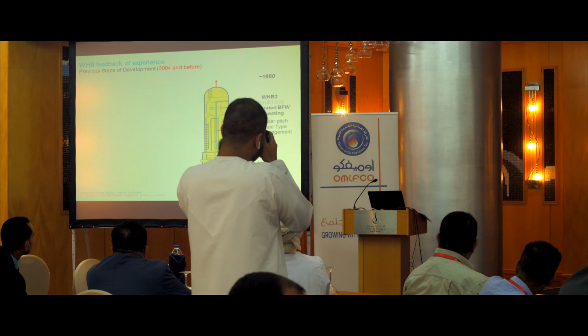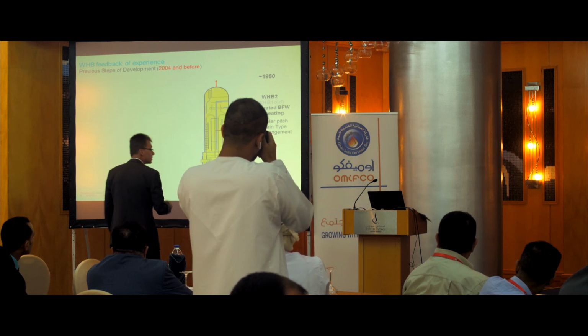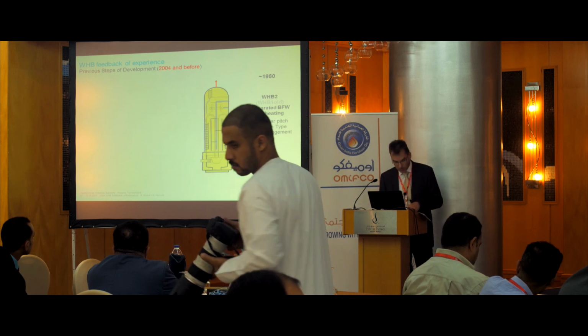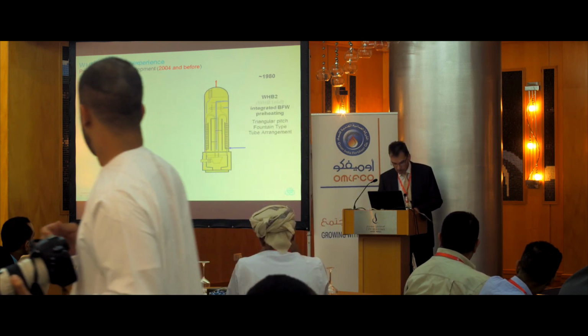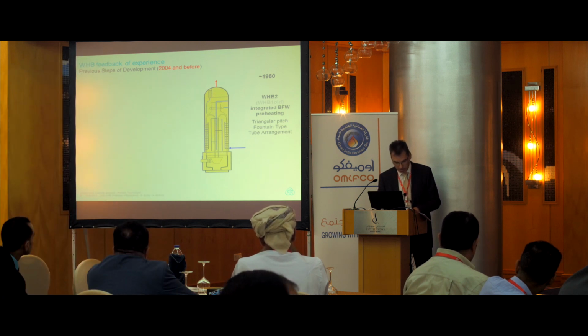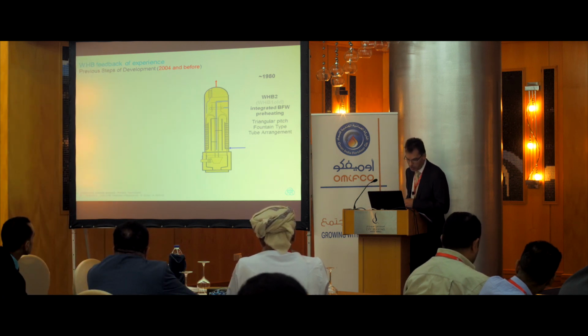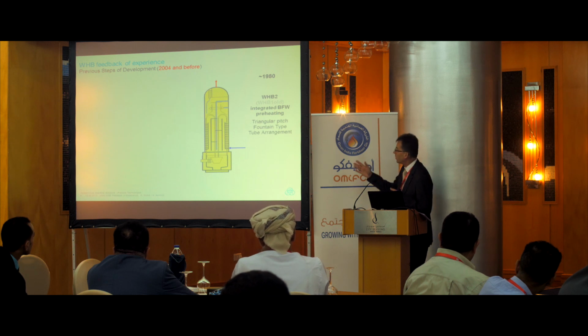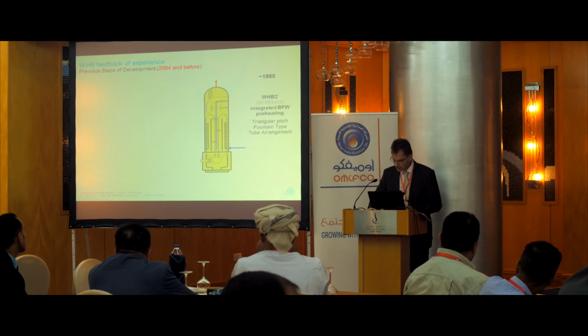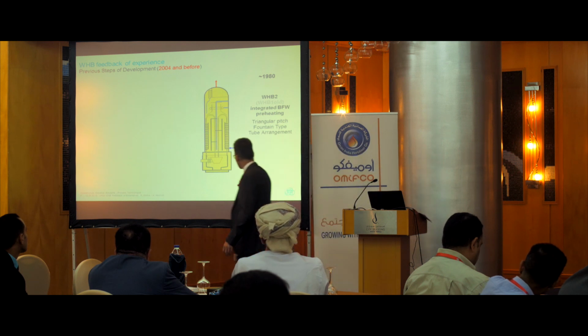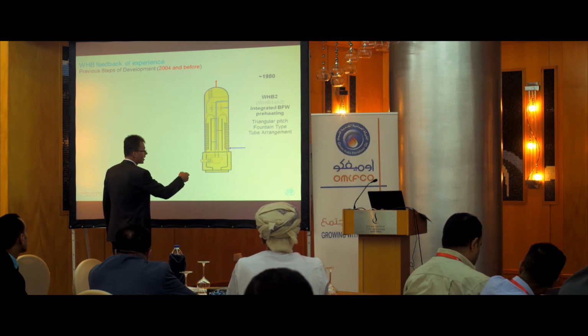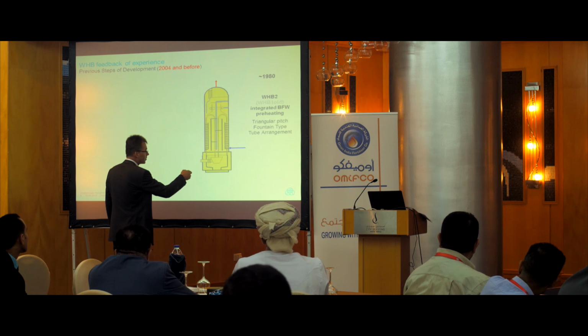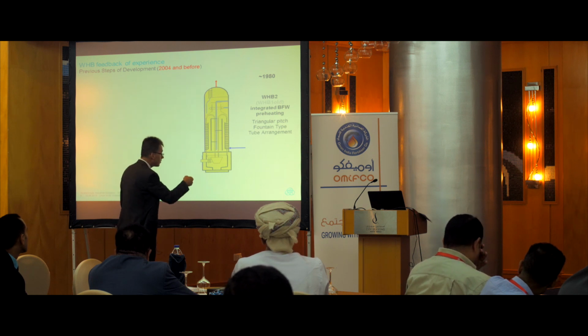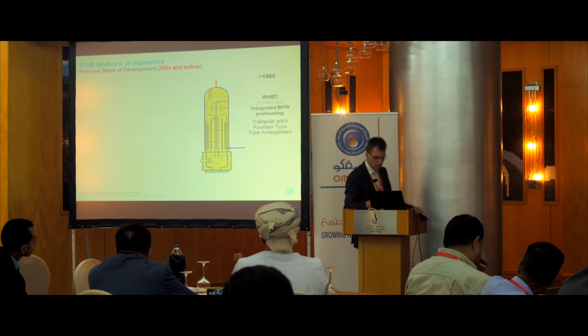In the middle of the tube bundle, you see here this gray area. This is a so-called intermittent blowdown. This blowdown is necessary to waste water from the boiler to avoid concentration of impurities during continuing evaporation of steam. The water is just blown out of the boiler with some forces by steam pressure within the boiler. There is no pump necessary. And it has a task. It's located very, very close to the tube sheet to get rid here of impurities, because here is the main collection of this, because it's a vertical boiler.